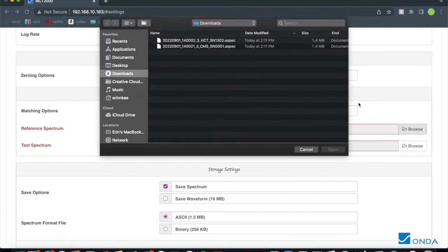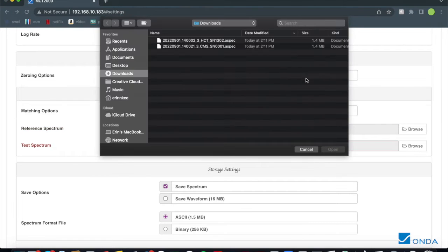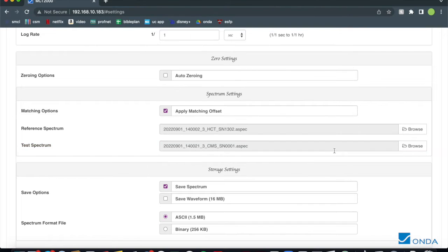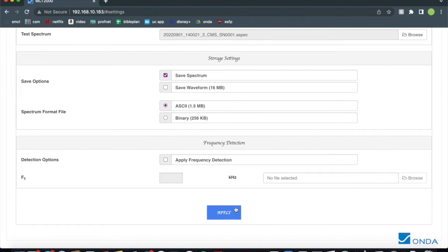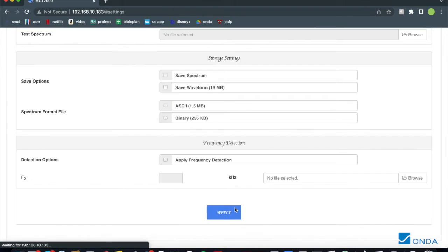The HCT320 should be the reference and the CMS should be the test. After matching offset is applied, press Apply. The CMS should now spectrally match with the HCT320.